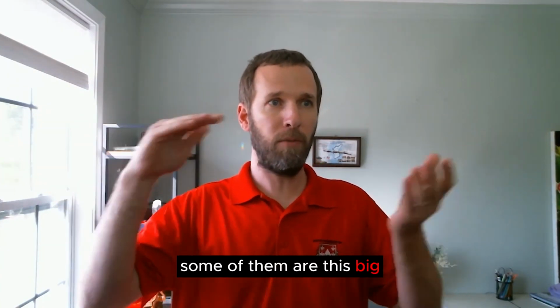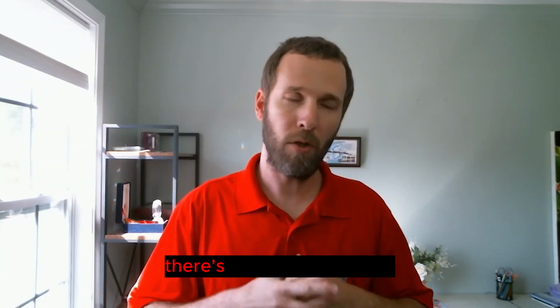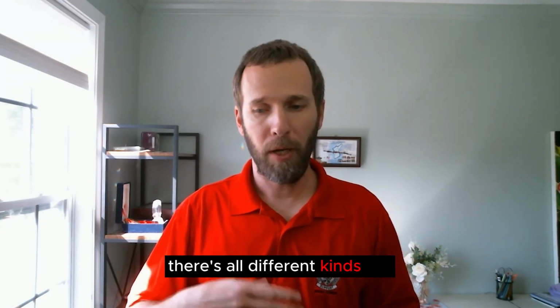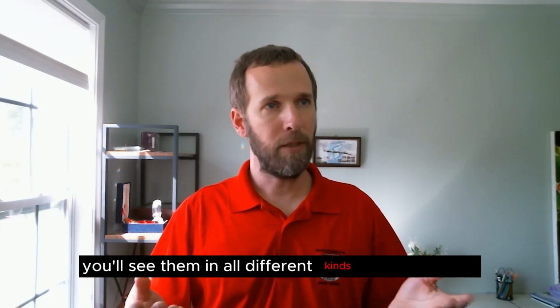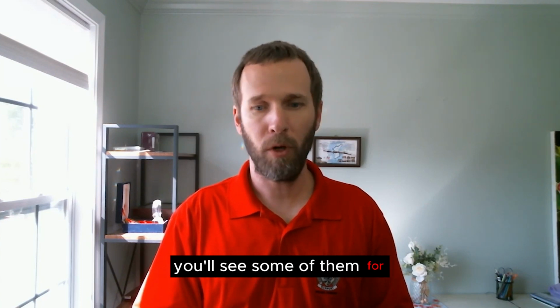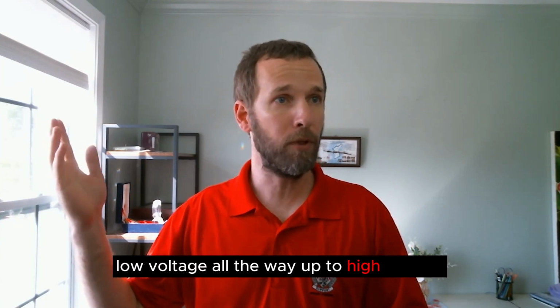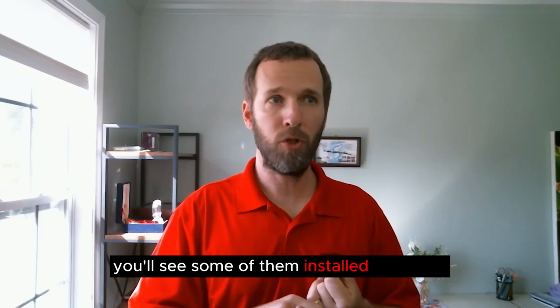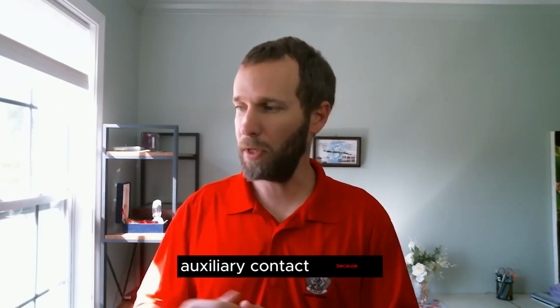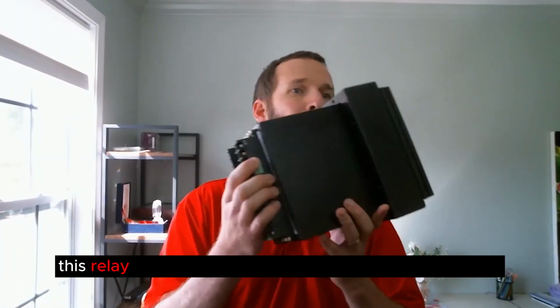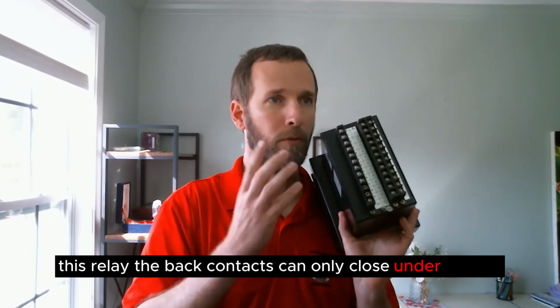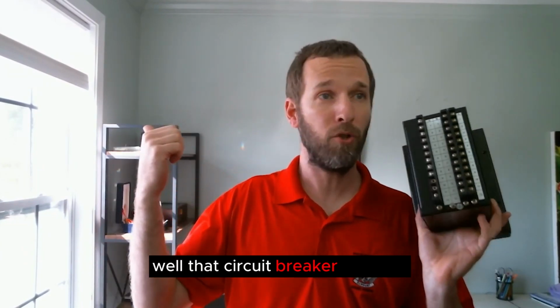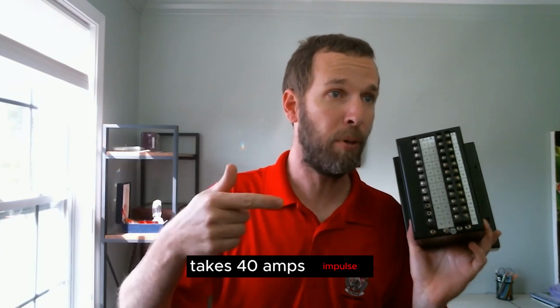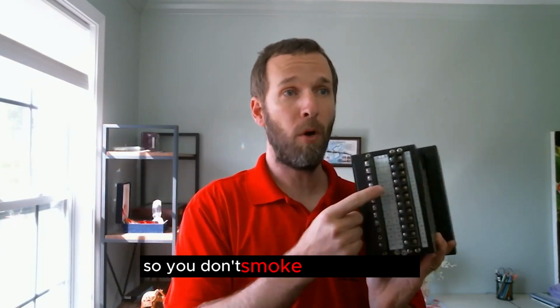Some of them are this big, some of them are this big. There's all different kinds, but you'll see them in all different kinds of applications - for low voltage all the way up to high voltage. You'll see some of them installed just as an auxiliary contact, because this relay's back contacts can only close under 5 amps. Well, that circuit breaker's trip coil takes 40 amps impulse, so it'll smoke these contacts.